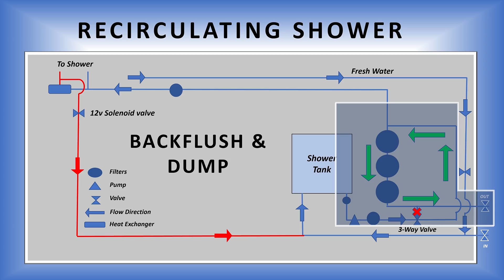Now, if I want to back flush my filters instead of just emptying the tank, I use this configuration with the 3-way valve. I turn and open the valve, which allows water to pass through here, come right back, and enter the back side of the filter. It can't go up to my shower because the shower valve isn't open — the solenoid valve is closed, so there's nowhere else for the water to go. So it goes down here, back flushes the filters, and comes right out the drain. That's a good way to back flush my filters, and it works really well.